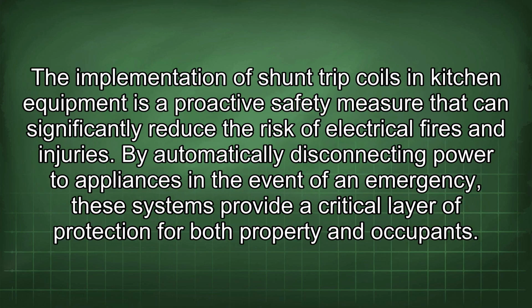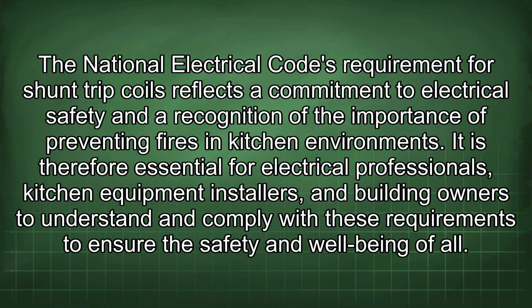The implementation of shunt trip coils in kitchen equipment is a proactive safety measure that can significantly reduce the risk of electrical fires and injuries. By automatically disconnecting power to appliances in the event of an emergency, these systems provide a critical layer of protection for both property and occupants. The National Electrical Code's requirement for shunt trip coils reflects a commitment to electrical safety and a recognition of the importance of preventing fires in kitchen environments.